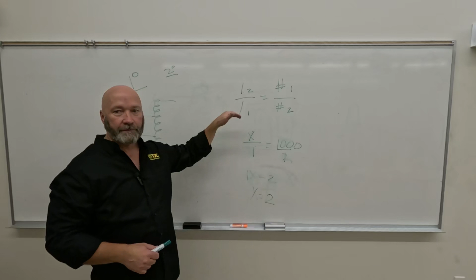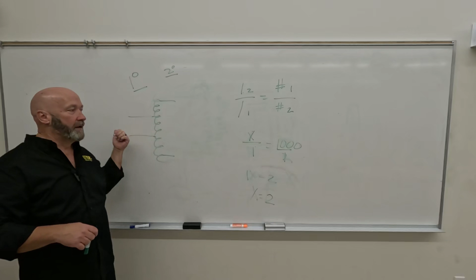So what's going to happen with your intensity or your amperage as your turns ratio changes? It's going to go down by how much? According to the turns ratio between the primary and secondary side. So if there are more turns on the primary side than on the secondary side, then your amperage goes down. If you have more turns on the secondary side than on the primary side, then your amperage increases. So it's an inverse relationship. It goes in exactly the opposite direction of voltage, but by the same magnitude, okay?